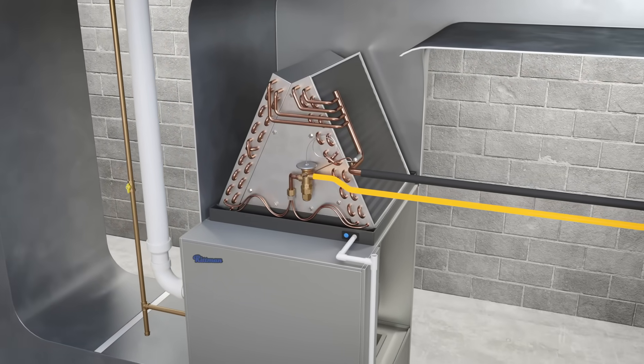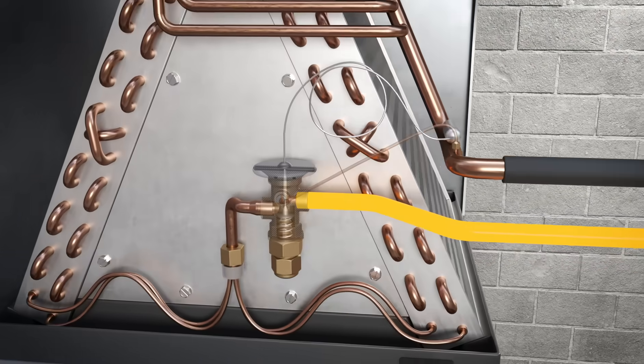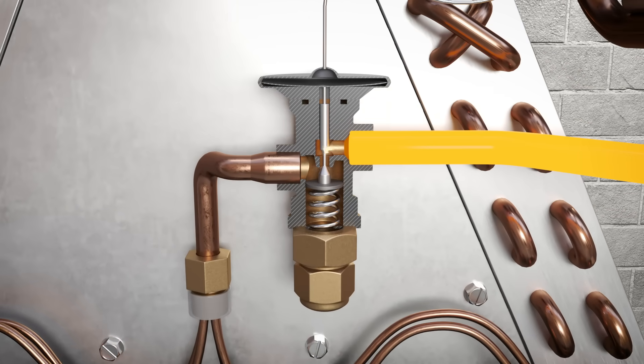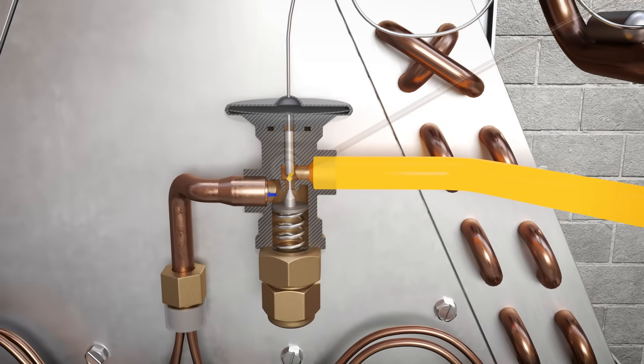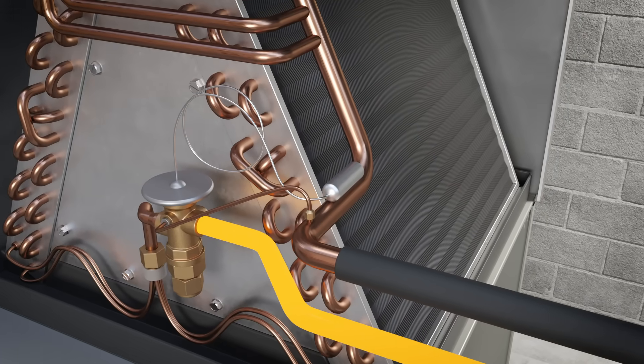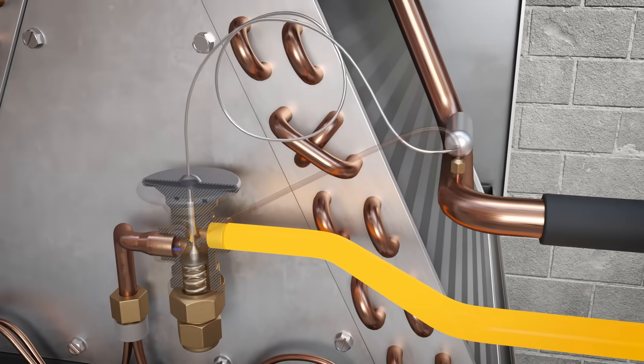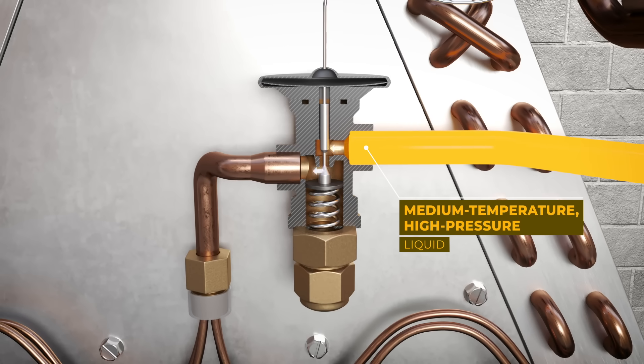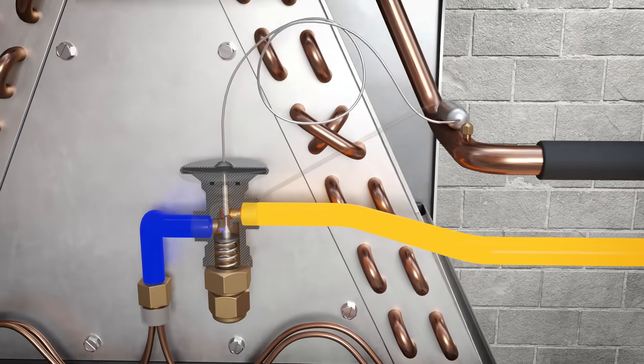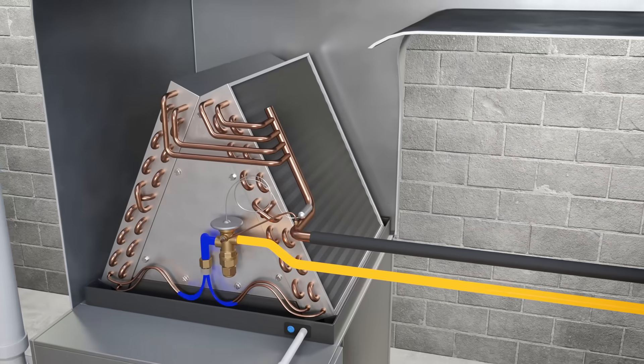The refrigerant then flows to the metering device — in this case, a thermal expansion valve is used. A pin inside the valve adjusts the flow rate of refrigerant depending on the temperature at the evaporator end, using a sensing bulb. As it flows through the valve, its pressure drops significantly, releasing a low temperature, low pressure liquid-vapor mix.